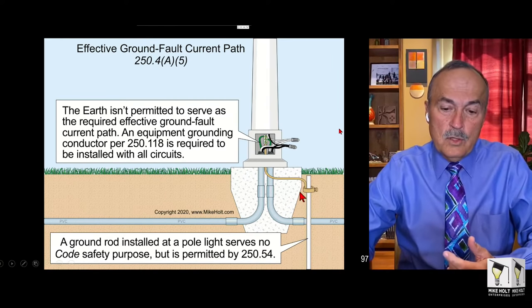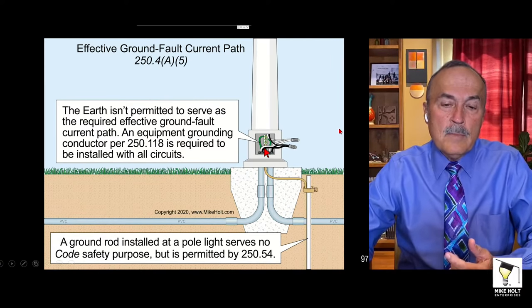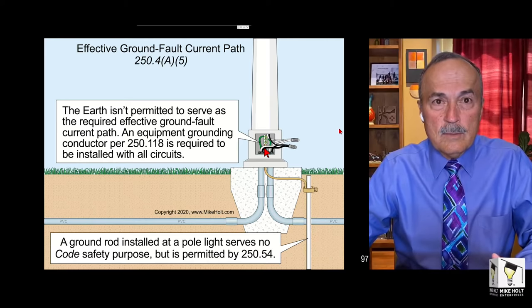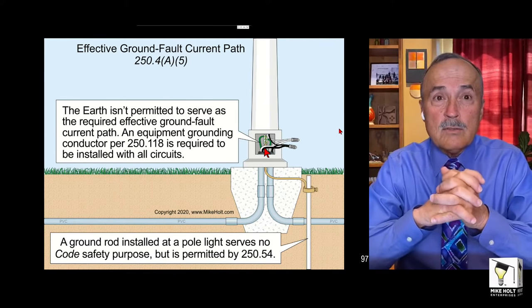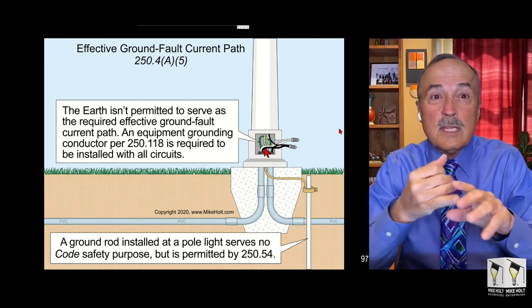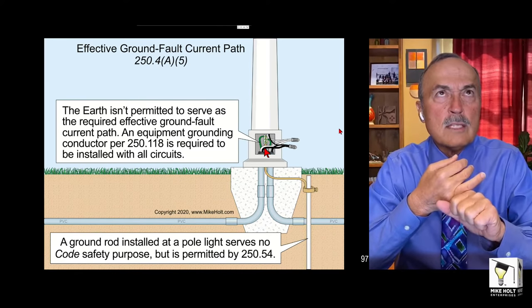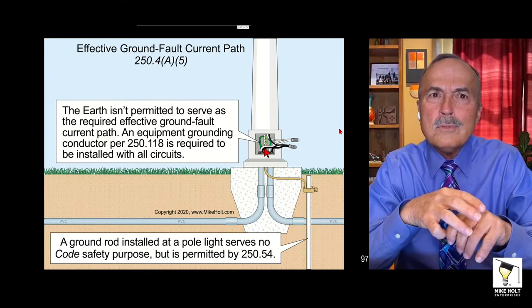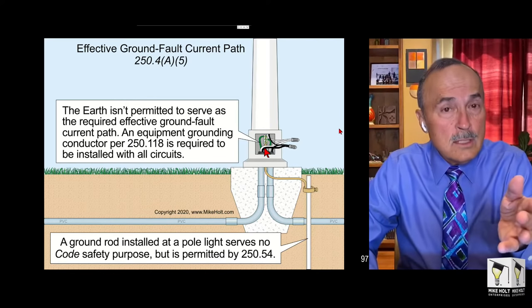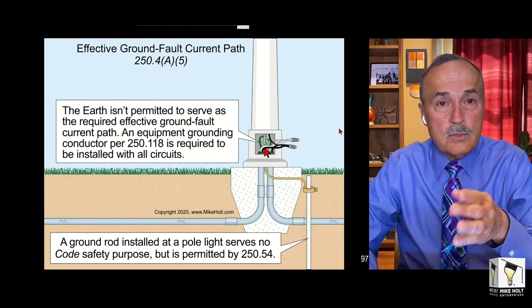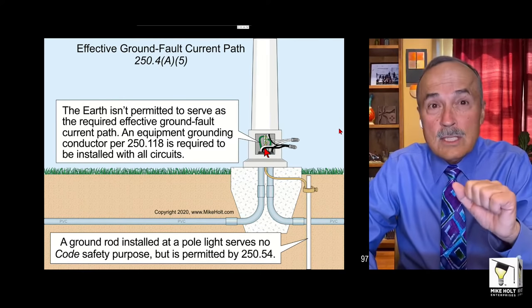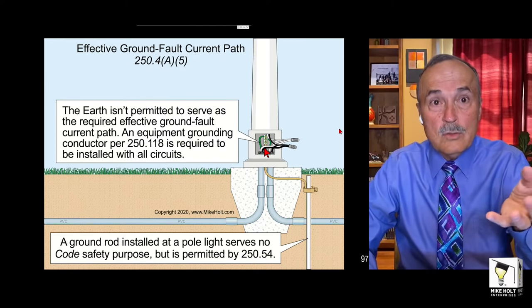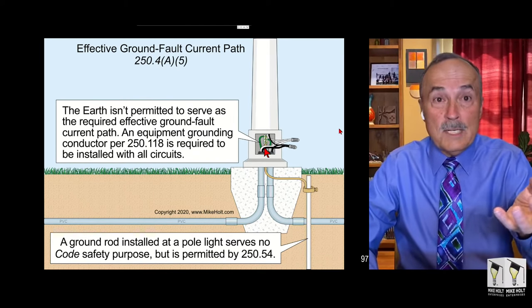The code allows you in 250-54 to install an auxiliary electrode. I've seen people put auxiliary electrodes next to motors, in pools, around pools. Now the code says if you want to add an auxiliary electrode, 250-54, you can. But you know what it also says? There are no rules. Why no rules? Because if you don't need to do something and the code says you can do it, there are no rules to follow.